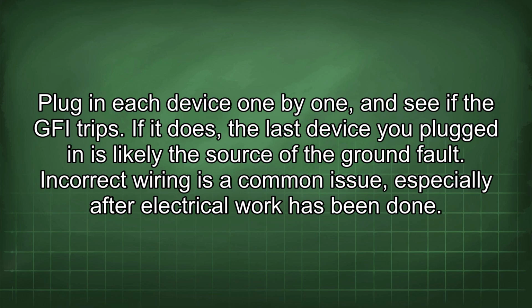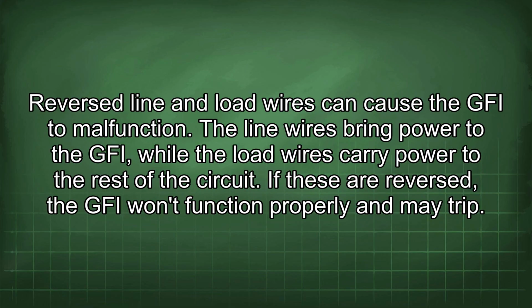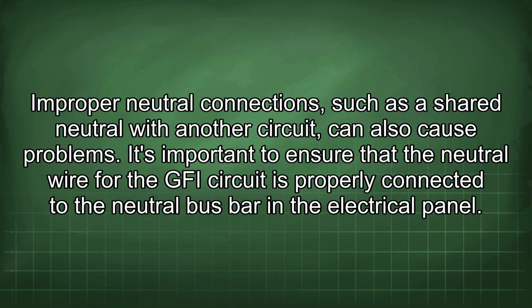Incorrect wiring is a common issue, especially after electrical work has been done. Reverse line and load wires can cause the GFI to malfunction. The line wires bring power to the GFI, while the load wires carry power to the rest of the circuit. If these are reversed, the GFI won't function properly and may trip. Improper neutral connections, such as a shared neutral with another circuit, can also cause problems.